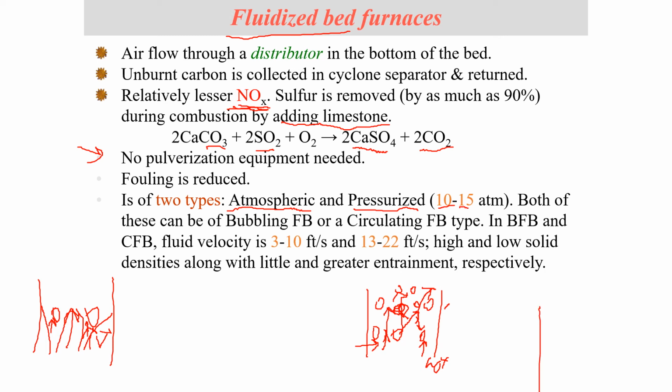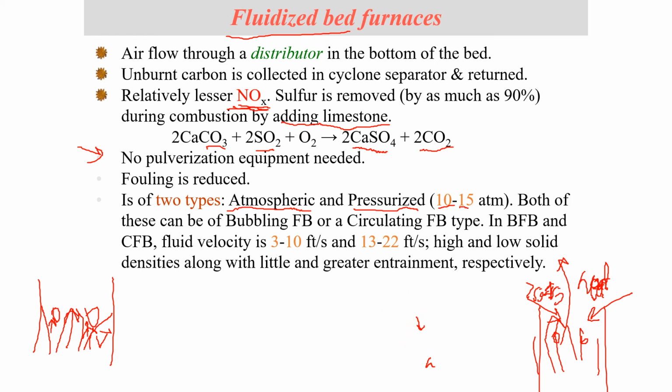So this actually means that there is a large flame and you're just dumping coal in, which is suspended in the air as it is burned and adds heat to the hot air for the boiler or whatever you are using. But again, this temperature is restricted to about 750 to 950 degrees Celsius because the volume of air is very large. So this is a very efficient kind of furnace, but again it has its restrictions.